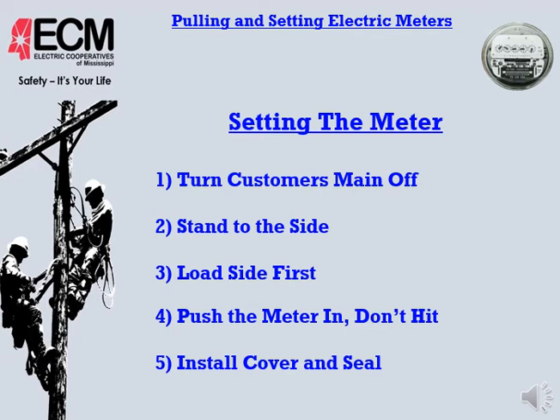Second thing we're going to do is stand to the side when we get ready to set a meter. We don't want to be standing in front of it. These meters are electromechanical, and the electronics in these meters could malfunction and we'd never know it or be aware of it. Electronic things fail, so we want to stand to the side just in case there's something we didn't catch. If this meter goes ballistic, we're not standing right in front of it when it goes haywire.